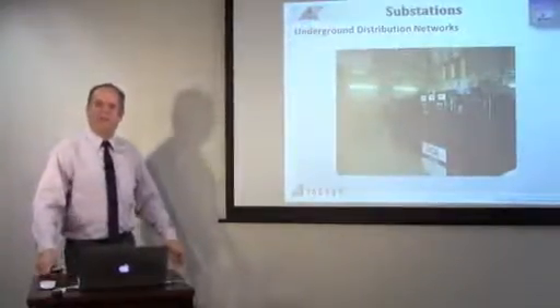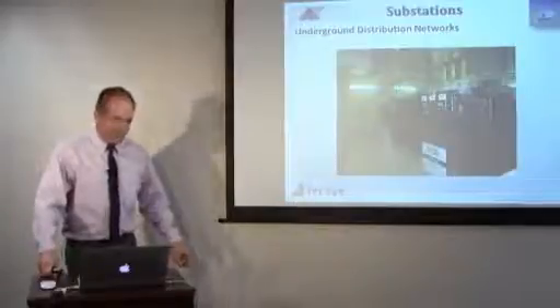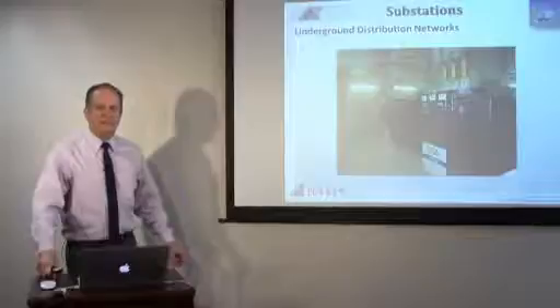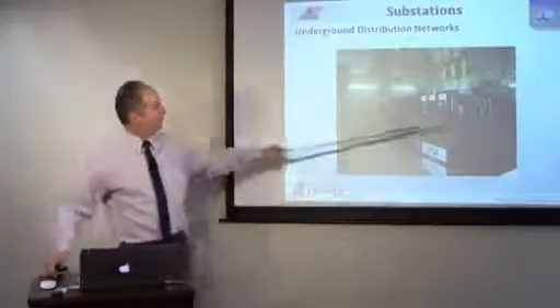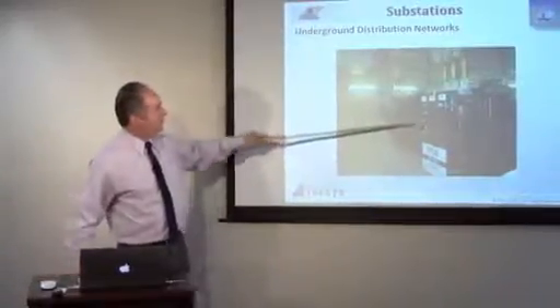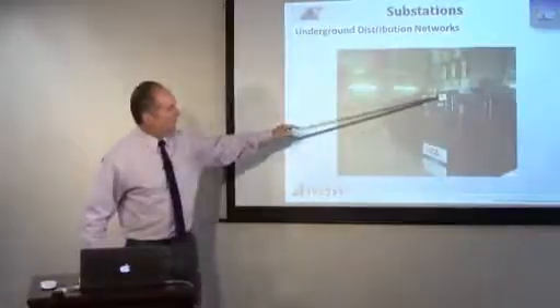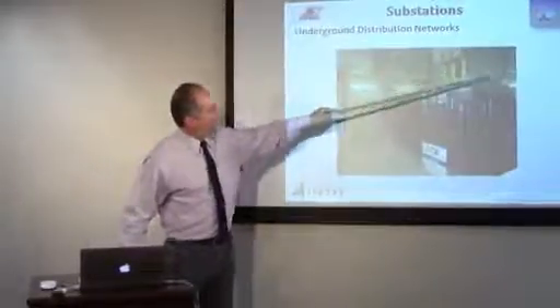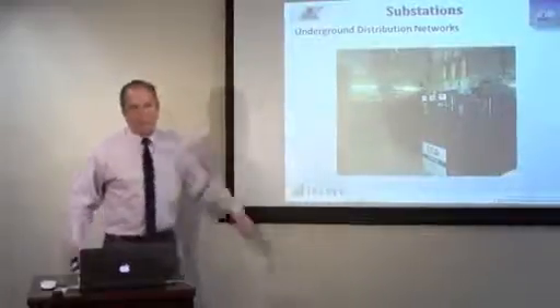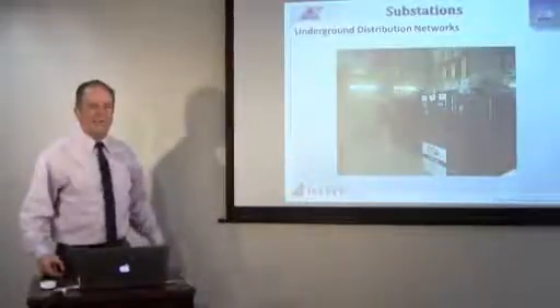Now, in underground distribution systems, in some of the very large cities, like the city of Los Angeles, Atlanta, Georgia, some of the larger cities, and not necessarily that large, you have underground distribution networks. And these transformers are three-phase. You can see the three phases, and there's the neutral for the grounded Y. And they operate 120, 208. So it's 208 three-phase. We'll get into that later in the distribution side.